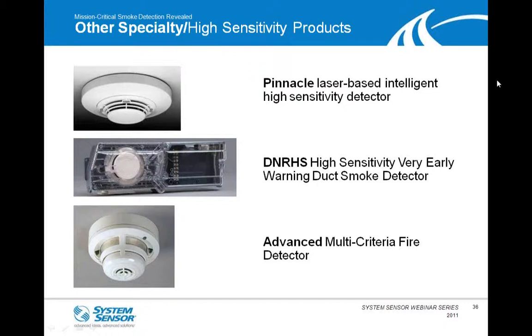Likewise, we do have our DNRHS, or our duct smoke detector, with that same Pinnacle high sensitivity detector within it. Again, ideal for return air grills. Prior to us launching this product, it wasn't uncommon for someone to have to put a multitude of either air aspiration piping in, or a handful, if not a dozen, spot detectors on a return air grill in order to provide the type of protection required. Duct smoke detectors in this application are a much more cost-effective solution to, again, meet that return air grill requirement. And then finally, another newer product that we offer is our advanced multi-criteria detector, which is using 4 different elements to, again, make better decisions, similar to FAAST, of whether or not we have a fire or just a nuisance-based condition.